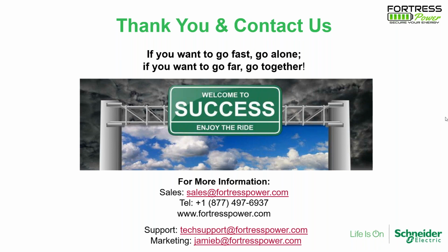Okay. In an area where there is no peak shaving or time-of-day kilowatt-hour cost difference, if a customer has an existing 8 kilowatt PV system, would there be any benefit to sizing the battery larger than the PV generation? If you want to take your customer off grid, that's a perfect situation. Again, that's case by case. If you want to do extended runtime for backup applications, yes, it definitely makes sense.